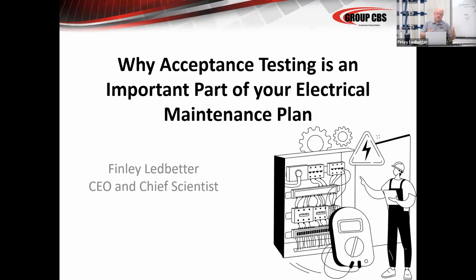Acceptance testing, you're basically starting with the new equipment, and then over a period of time, okay, you'll test it again and you'll start maintenance testing. In that period of time, how do you feel comfortable the equipment will perform? Testing really doesn't do that for you. Testing only tells you today. So how do you basically prove that out to where I feel comfortable that my equipment will properly perform over this length of time? Is that 1 year? Is that 2 years? Is that 5 years? We'll get into that maintenance cycle and how to determine what that time should be in the maintenance part of the presentation, which will be in a month or two.